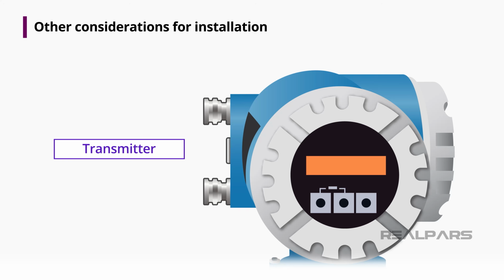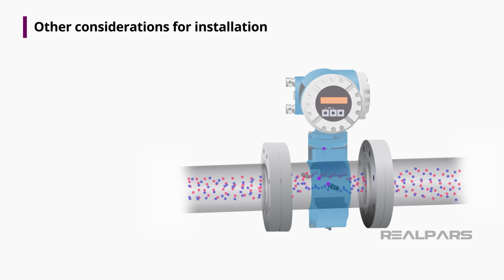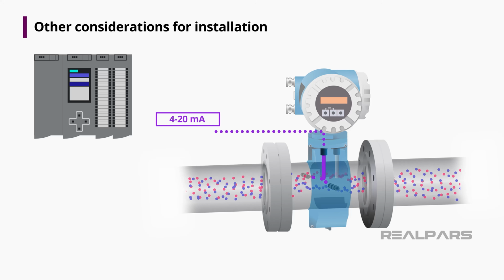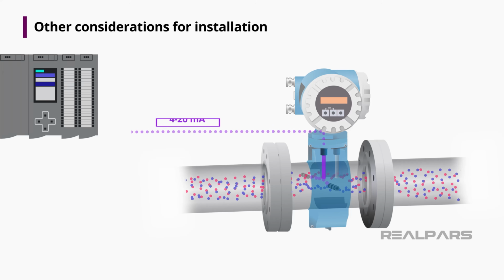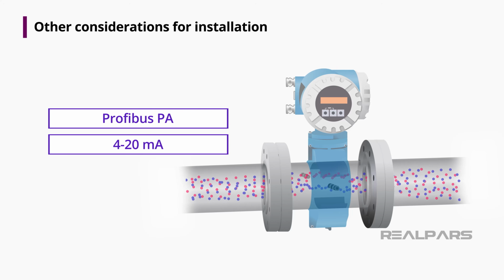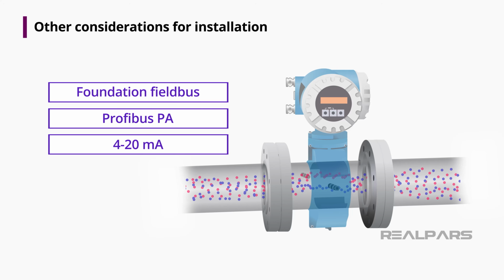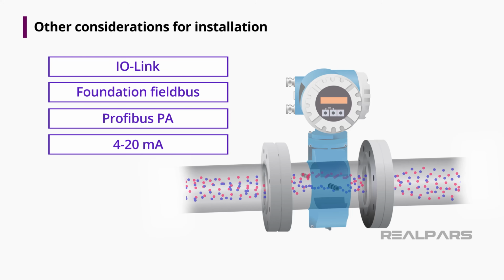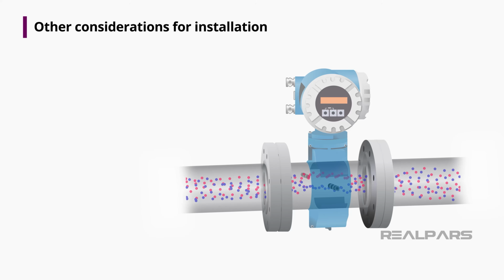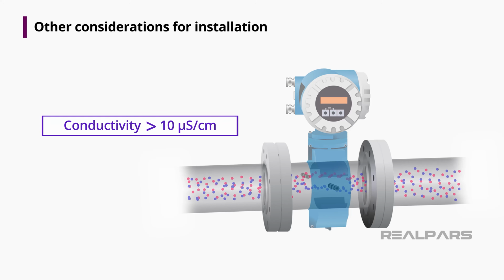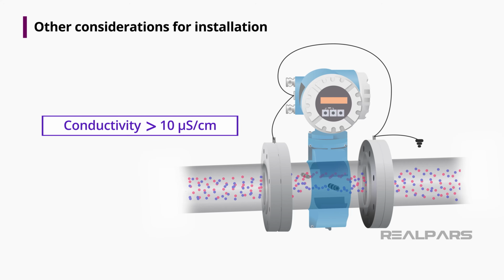Transmitters are always used with mag meters. They convert the small DC voltages generated by the flowing fluid into signals that can be connected to the control system. 4 to 20 milliamp, Profibus PA, Foundation Fieldbus, and IO-Link transmitter outputs are available. When specifying magnetic flow meters, some important aspects must be considered in addition to the conductivity of the fluid and the need for grounding rings. If the fluid is corrosive or abrasive, a compatible liner should be specified. These liners can also be replaced if they become worn, and they do not affect the measurement accuracy.